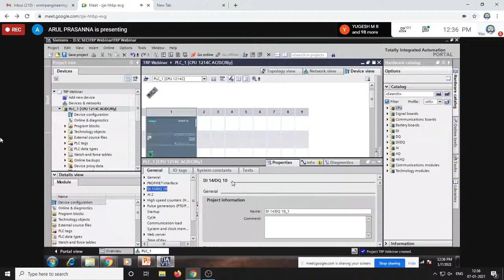So 14 means starting address will be I0.0 and ending address will be I1.5. That's I0.0, 0.1, 0.2 up to 0.7, 8 terminals, then I1.0 to 1.5, around 6 terminals. So 8 plus 6 gives us 14. Similarly for output 10, that means Q0.0 to 0.7, 8 terminals, then Q1.0, 1.1, 2 terminals.